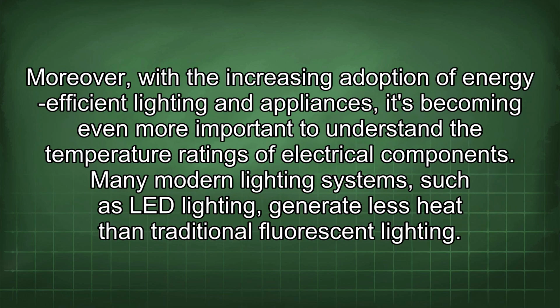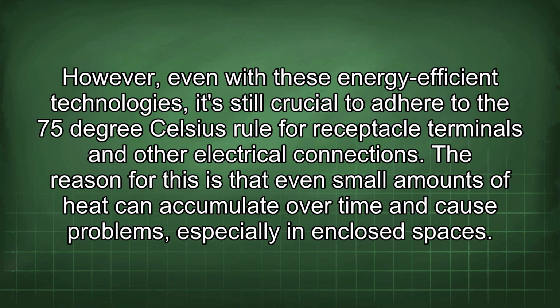Moreover, with the increasing adoption of energy-efficient lighting and appliances, it's becoming even more important to understand the temperature ratings of electrical components. Many modern lighting systems, such as LED lighting, generate less heat than traditional fluorescent lighting. However, even with these energy-efficient technologies, it's still crucial to adhere to the 75°C rule for receptacle terminals and other electrical connections.